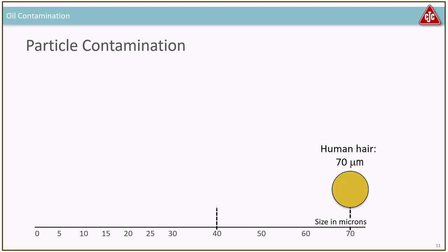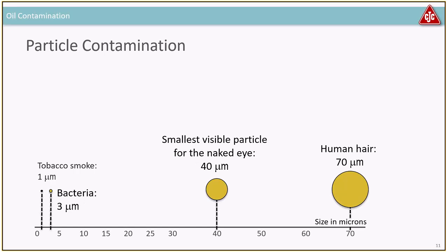The three main contamination types we'll look at: first, particles. The problem with particles is that you cannot see the ones that are harmful. The diameter of a human hair is around 70 microns — a micron is one thousandth of a millimeter. A dust particle is roughly 40 microns. In oil you can only see a particle of 100–150 microns or bigger. The majority of harmful particles are actually in the region of 1 micron (tobacco smoke size) or 3 microns (bacteria size).